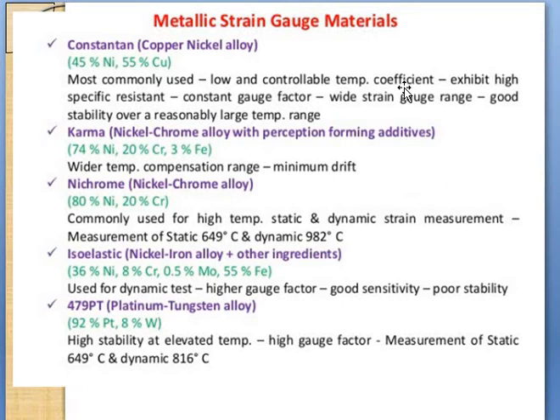Nichrome is commonly used for high-temperature static and dynamic strain measurement. For static measurement it can be used up to 649°C, and for dynamic loading up to 982°C. Isoelastic material is mainly used for dynamic tests — it has a high gauge factor and good sensitivity but poor stability. Platinum-tungsten (Pt-W) is used for elevated temperature applications.